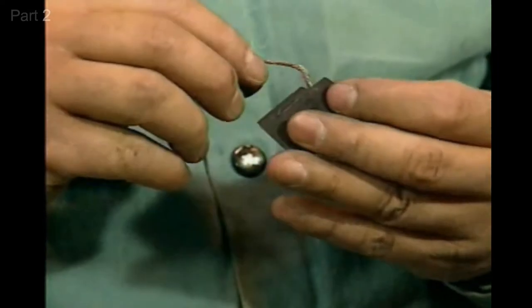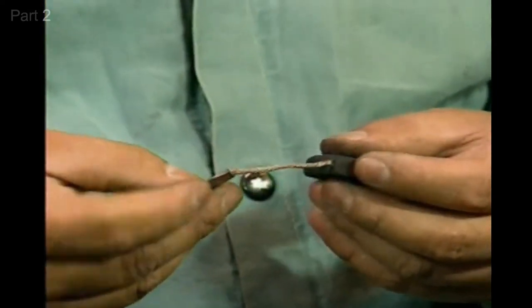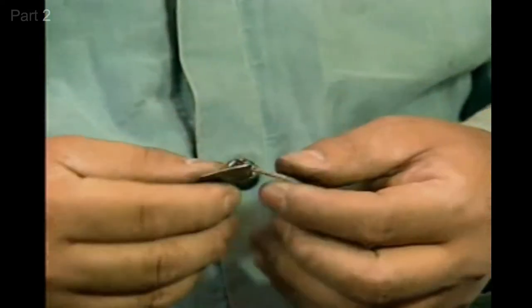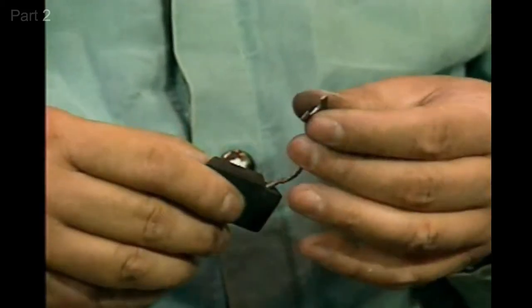The brush pigtail should be securely fastened to the brush. The pigtail should be flexible and it should not be frayed or discolored.